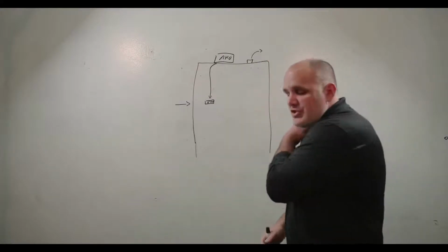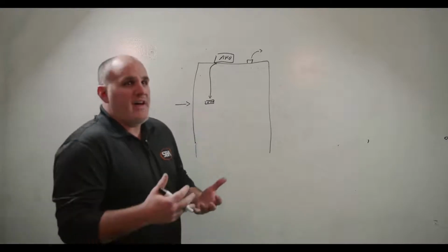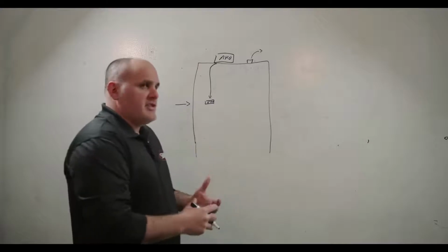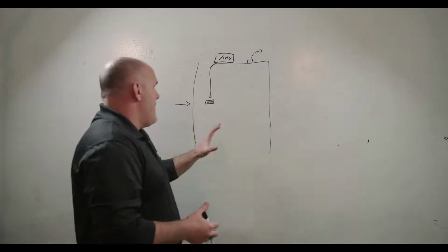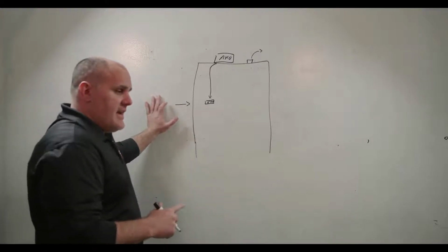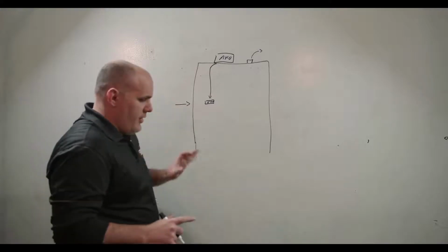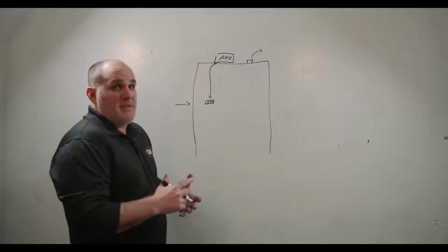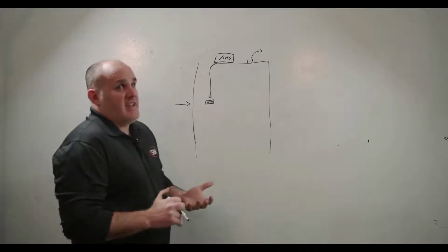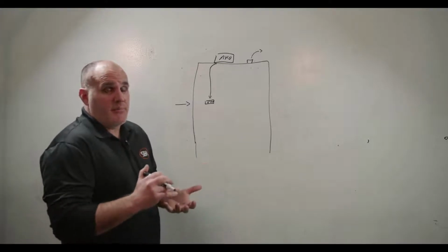Now, how do we control pressure? There's a variety of different ways we control pressure. We have what's called volumetric offset and matching. That is a flow-centric pressure strategy. And what we will do is we will measure the flow that is going in and the amount of flow that's coming out, and we will either match, and we will say, okay, we're going to match flow, and that should keep us at a kind of normal pressure, or we're going to do an offset, either a negative or a positive offset, depending on how we want to influence building pressure.